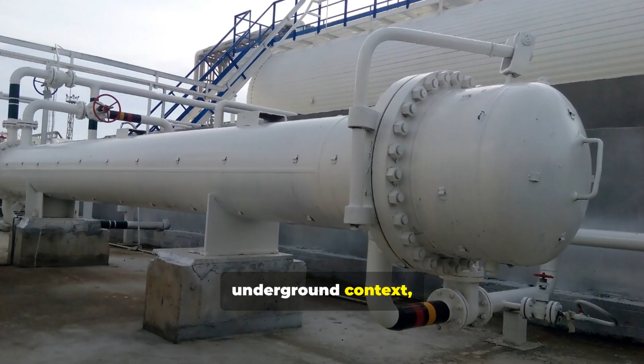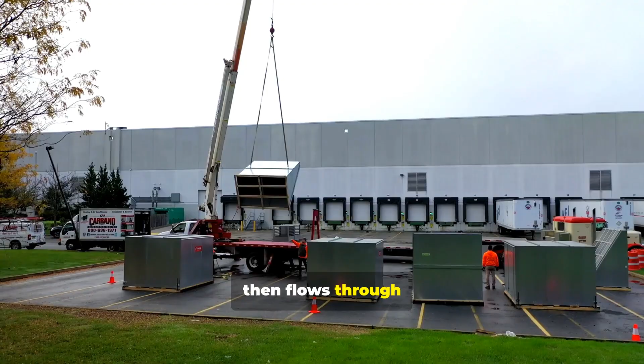In the Finnish underground context, water can be circulated through a heat exchanger that is cooled by the surrounding rock or by outside air during the colder months. This chilled water then flows through pipes to the data hall, where it absorbs heat from the servers via computer room air handler units. This process uses only the energy required for pumps and fans, a fraction of what a traditional refrigeration cycle needs. This approach leads to a dramatic improvement in the data center's power usage effectiveness, or PUE.